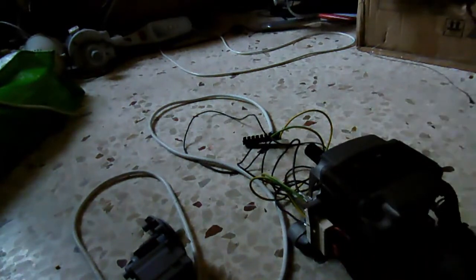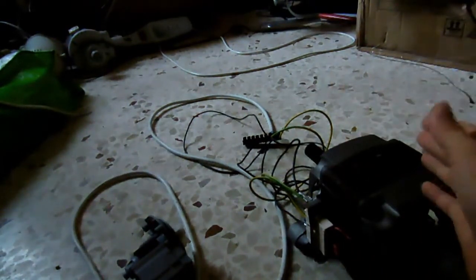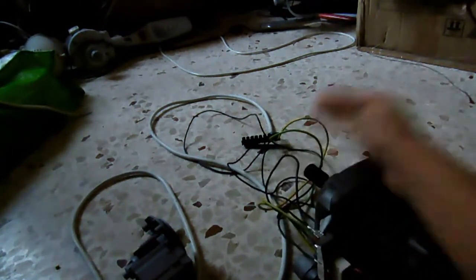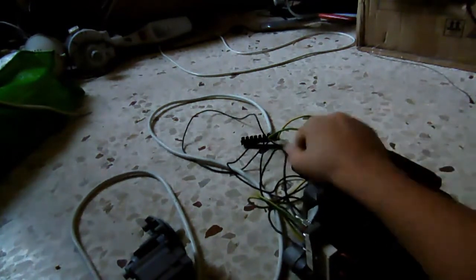But alas, the voltage is too high to be measured on a multimeter. And no, this is not inductive spiking - the high voltage is not generated via inductive spiking. It's generated via the generator principle: the moving conductor, the armature, generating electricity from the magnetic field generated by the field winding.